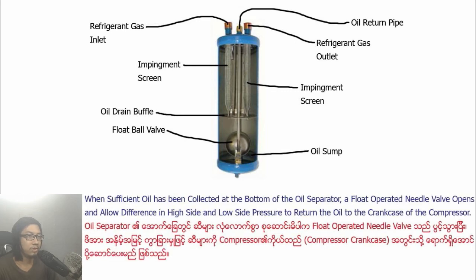When sufficient oil has been collected at the bottom of the oil separator, a float valve opens and allows the high-side to low-side pressure differential to return the oil to the crankcase of the compressor.